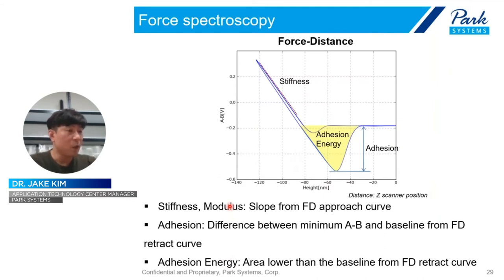From this FD curve, we can obtain several mechanical properties. For example, stiffness or modulus from the slope of the FD approach curve, and the adhesion value, like adhesion force or energy, from the retract curve. Also, sample deformation, energy dissipation, or approach and retract stiffness can be calculated from just one FD curve.